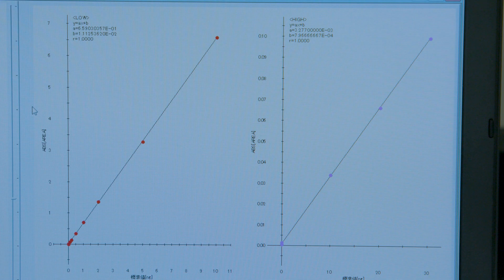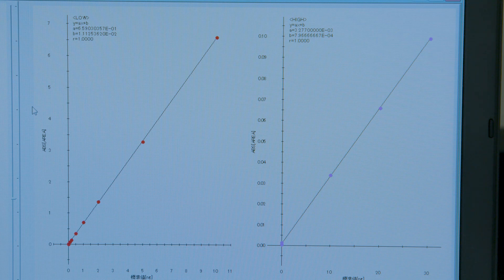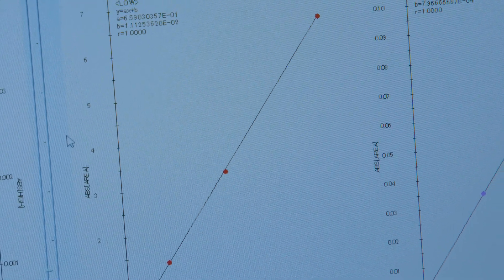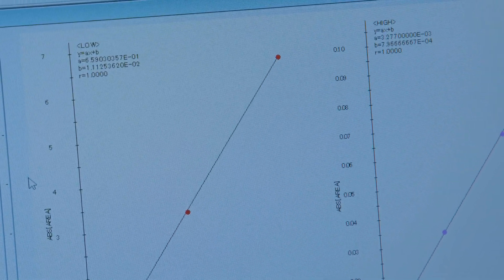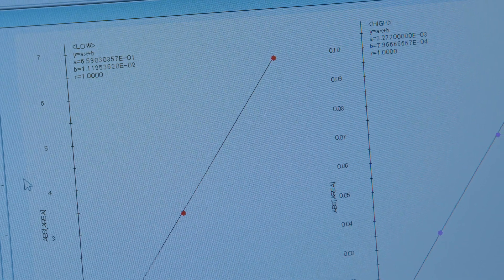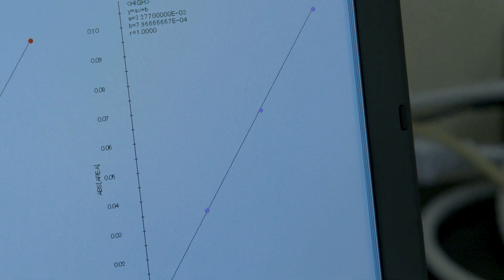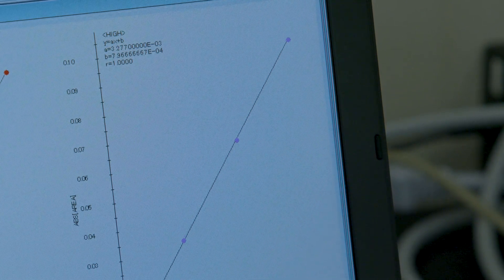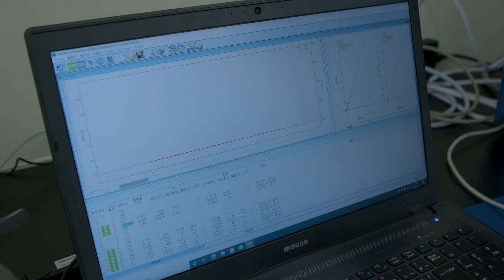Ensure that calibration is accurate before measuring the samples. We should ensure that calibration spans a useful measurement range. Generally, we need at least three calibration points for each absorption cell, covering a range of 0-10 nanograms and 10-30 nanograms. The total mercury concentration in hair from a non-exposed population is typically between 0.1 and 0.7 nanograms per milligram. If someone consumes a lot of fish, their concentration can be higher, circa 1-3 nanograms per milligram.